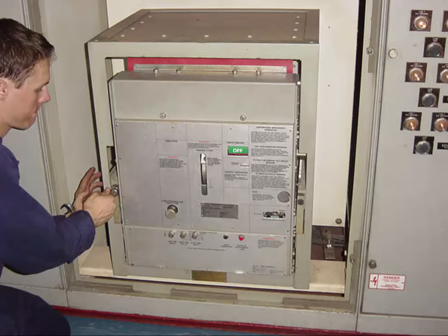So these are allowed to prevent a blackout situation if you have a generator that is overloaded for a short period of time. These breakers, by the way, can open large current flows. These are typically designed somewhere around 100,000 amp. It can open safely without damage. And to do this, these are motorized. In other words, they have springs that close and open these circuit breakers. And they typically have an electric motor to do this. So this type of circuit breaker usually has to have an outside low voltage source.